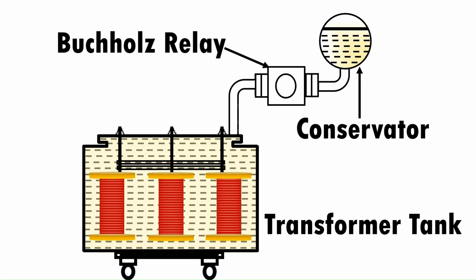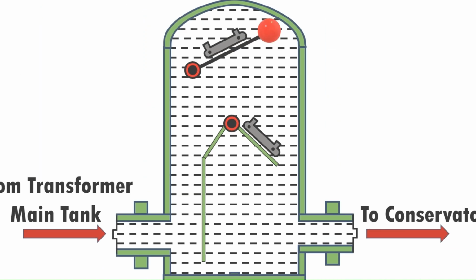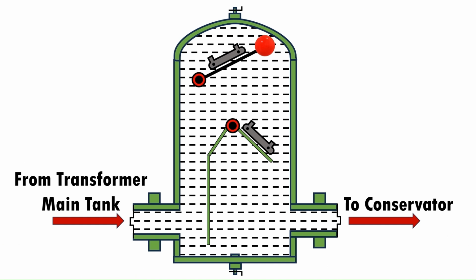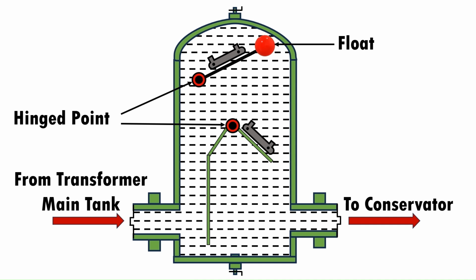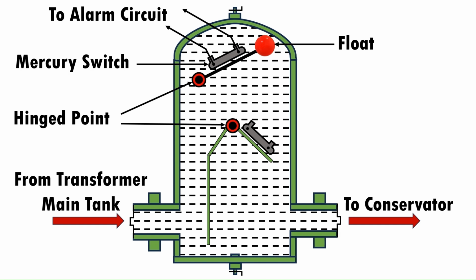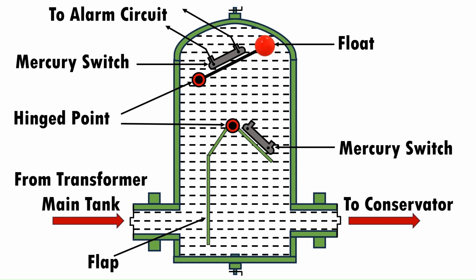Now, we will see construction and working of Buchholz relay in detail. It has mainly two elements. The upper element consists of a float. The float is attached to a hinge in such a way that it can move up and down depending upon the oil level in the Buchholz relay. One mercury switch is fixed on the float. This mercury switch is used for activating the alarm. The lower element consists of a flap and the mercury switch on it, which energizes the trip circuit.